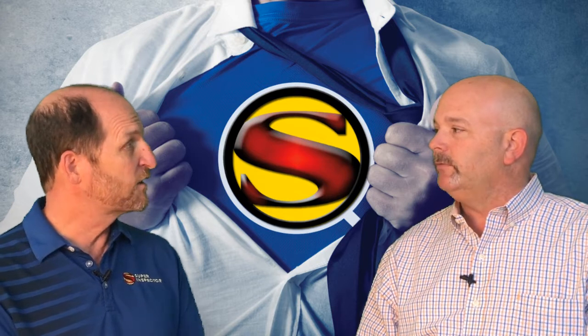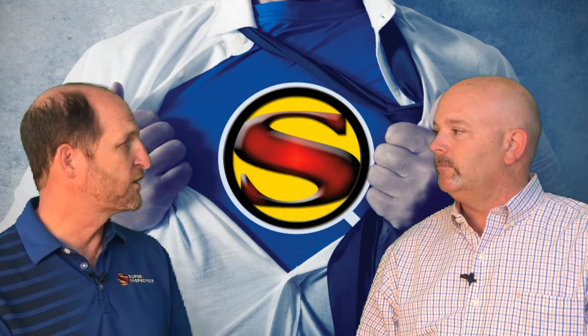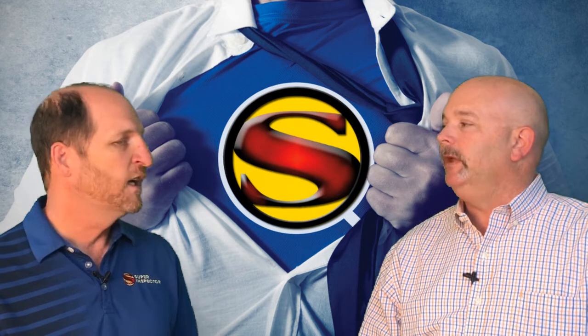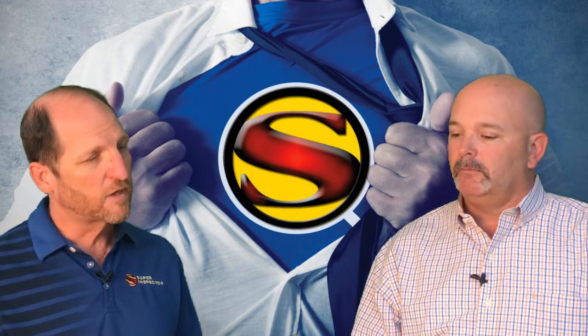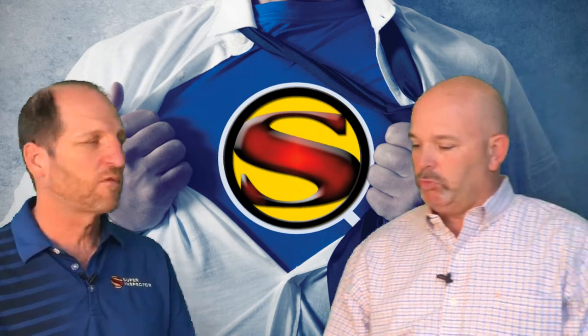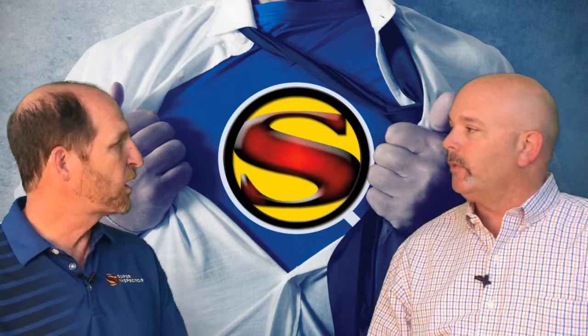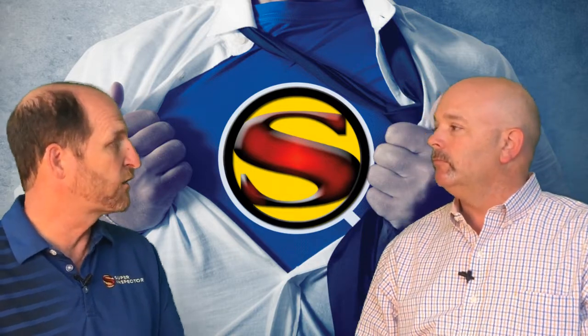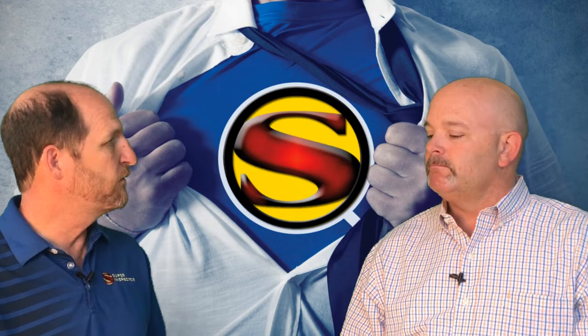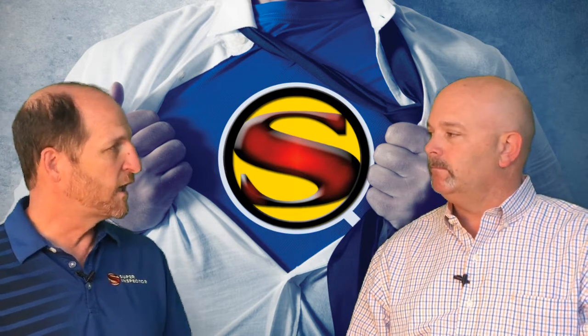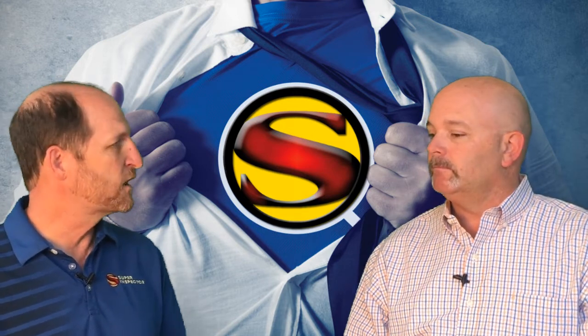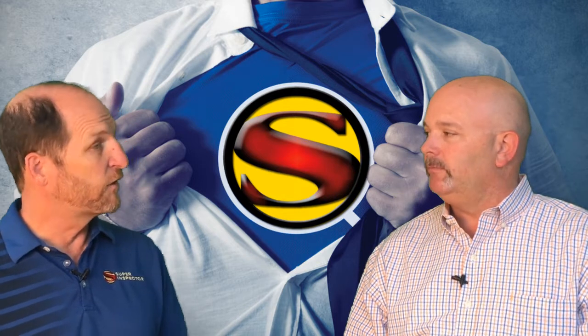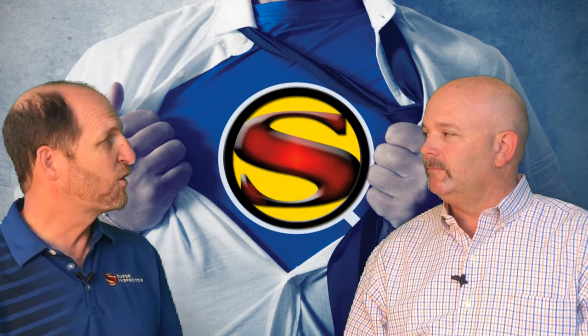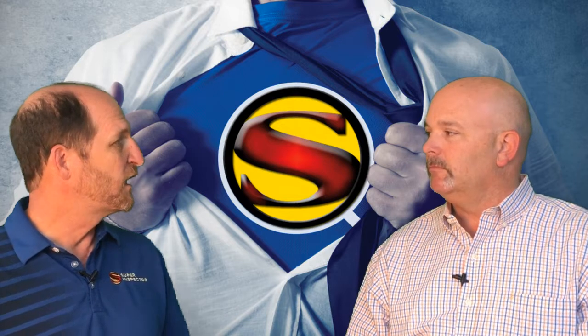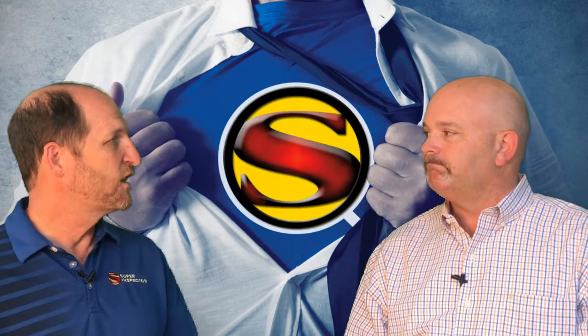If it sits in there too long, then that water ends up on the ceiling because it rusts through. So when we go in, it's very common to see rust in the pan, and we don't know if that's a current problem unless we actually see water there, or if it's from a previous issue. Either way, the rust compromises the integrity of the pan. If it was from a previous issue and new water starts to go in there when things change, it's going to rust through very rapidly. So that pan really should be changed out.